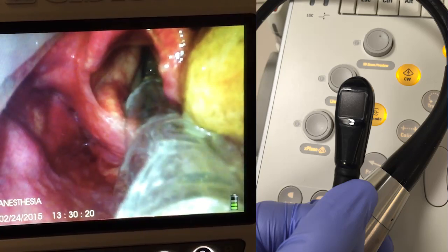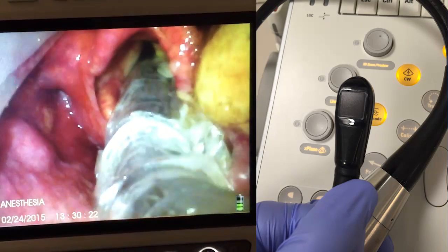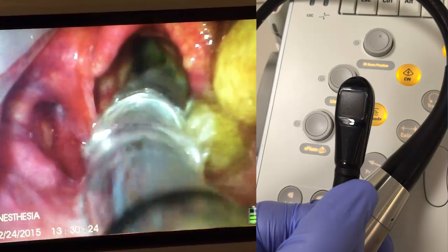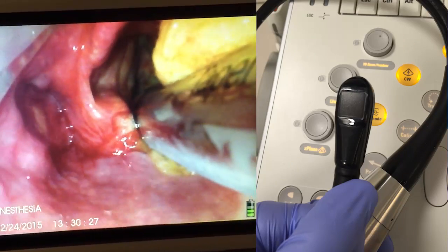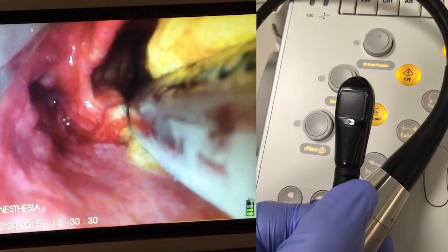On the right is a TEE probe. The reason I put that TEE probe is because the main thing you want to look at is the surface of the probe. On that surface, if you take a look, there's actually a scratch on it. When we put bite blocks in the patient's mouth, as you pull the TEE probe out, you can cause a bite mark on the probe and scratch the surface. Each probe is about $25,000. When there's a scratch on the surface of the probe, that probe is not going to operate for a 6-hour MitraClip case. So you always want to check the probe surface before you put the probe in, or else you better have gone to the bathroom before you went to the MitraClip case.